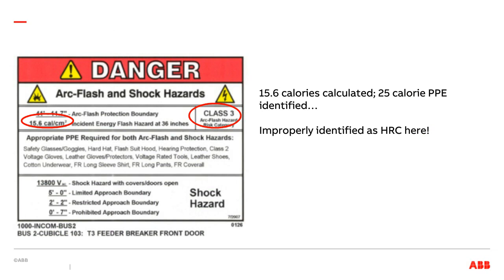Here is an arc flash label where the data may be described here to tell you 15.6 calories. They use class 3 arc flash hazard risk category, which, by the way, they never should have done. That's a wrong use of the term arc flash risk category, but it was a very common mistake years ago. Regardless, this means 25 calorie PPE when the exposure was actually 15.6. There's a margin of about 9 to 10 calories. Assuming you are okay with shrinking that margin, the question is, is 25 calories going to be enough for the new exposure?